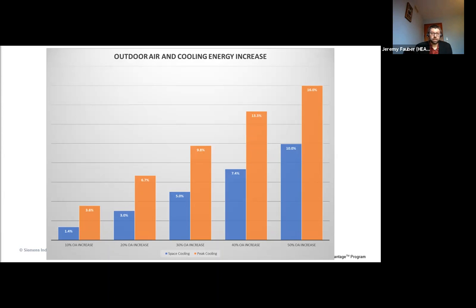But at that 10%, you look at all the hours where it's slightly above that, it only equals a 1.4% increase in cooling energy used throughout the entire year. However, we see with the orange the impact that it has to the peak that is required of that equipment. So we can see with this that overall, it doesn't have a huge percent increase in energy compared to what it uses throughout the year, but it does impact the peak. I would expect a normal piece of equipment sized by most engineers could probably handle a 10% increase, which in this case is just taking you from 24% outside air to 26, 27% outside air.